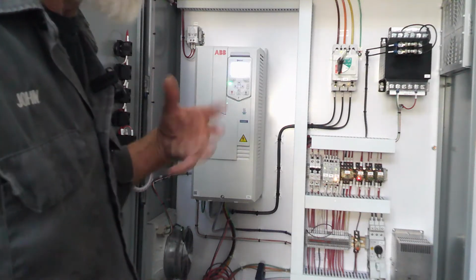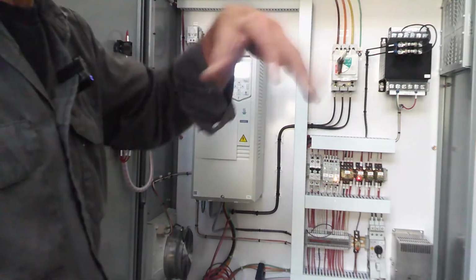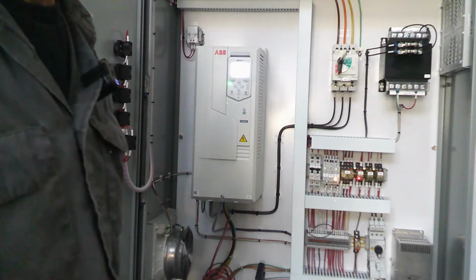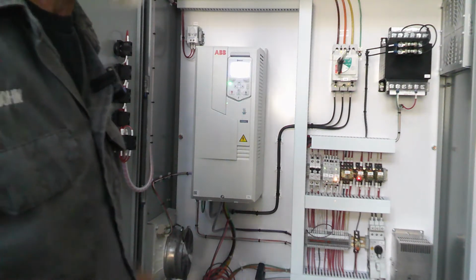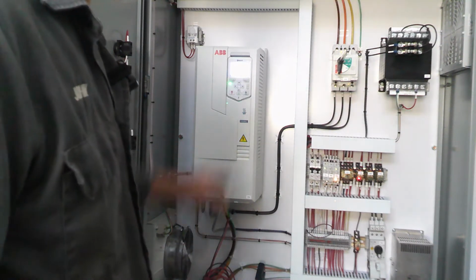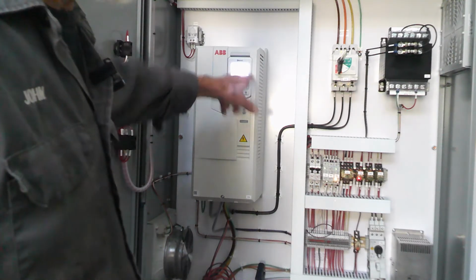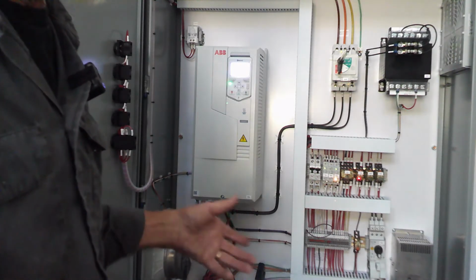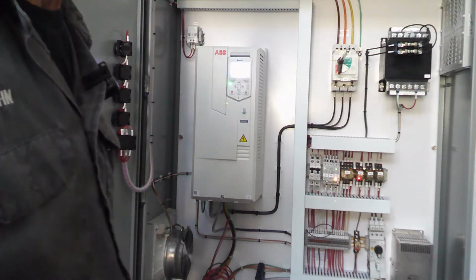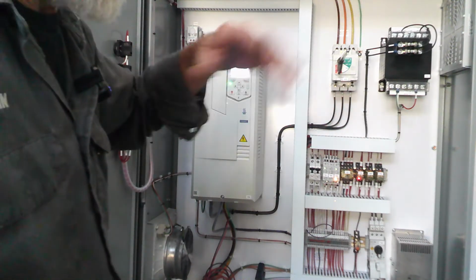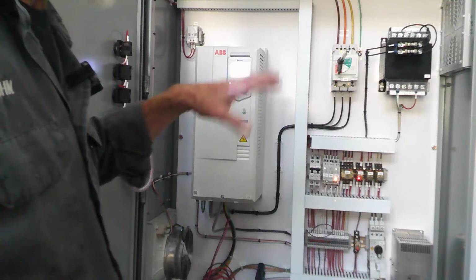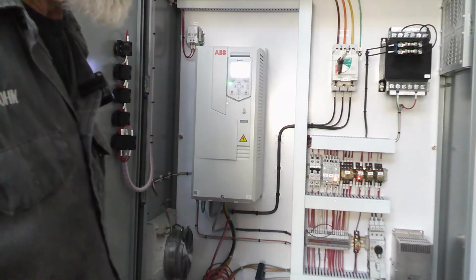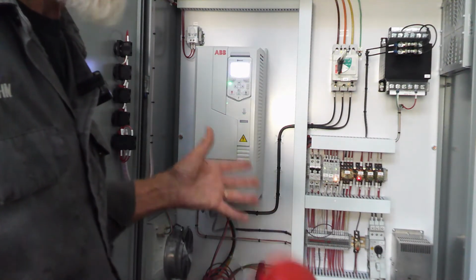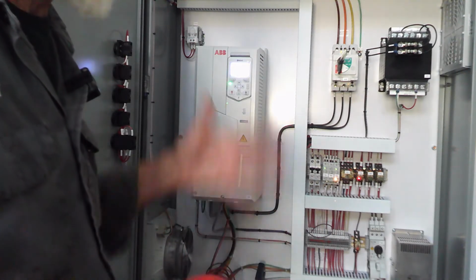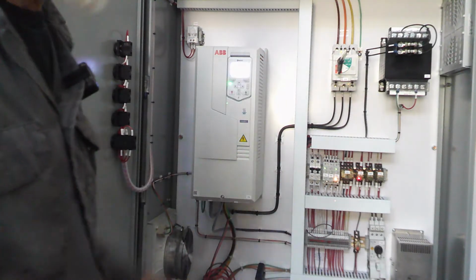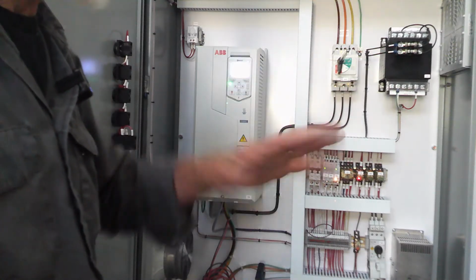It also keeps somebody not familiar with it from going in there and screwing around with stuff, because if you know something, you'll eventually figure it out. That's why this is full, but full will mean whatever the maximum and minimum have been set at, and they set them both at 57. Typically they're on the high side, it's engineered rather closely, and the ones I've seen will be 55 to 60 hertz. They put a motor in that'll just do what they want it to do, no excess.